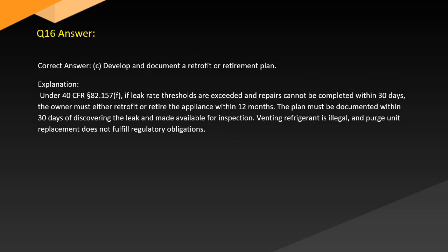Answer. Correct answer. C. Develop and document a retrofit or retirement plan. Explanation. Under 40 CFR 82.157(f), if leak rate thresholds are exceeded and repairs cannot be completed within 30 days, the owner must either retrofit or retire the appliance within 12 months. The plan must be documented within 30 days of discovering the leak and made available for inspection. Venting refrigerant is illegal. Purge unit replacement does not fulfill regulatory obligations.